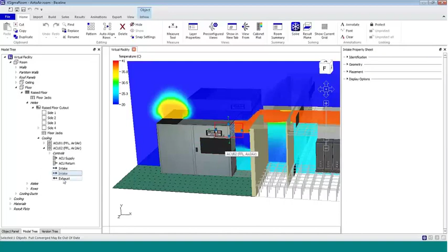You can also further cool that air by making it water cooled. So if the outside air temperature is really hot and you're not meeting your set point, you can use a trimming coil — a water spray, a cooling pad, or even a DX coil downstream — to cool the additional air.